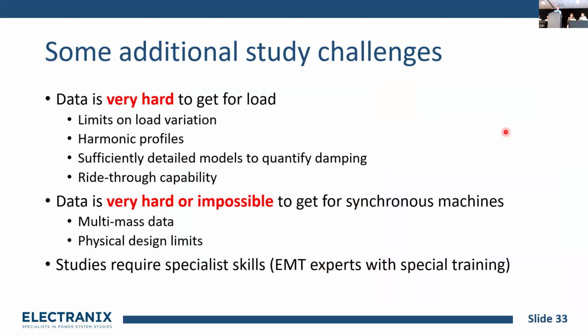With these studies, we don't have that right now. Data is very hard to get, first of all. Load variation limits are very difficult to get and sometimes unknowable. Harmonic profiles are sometimes unknown, at least early on. We don't have sufficient model quality to evaluate damping in the system right now, and there are other model issues - that's another topic we're not going to get into, though a later presentation might talk about it. Ride-through capabilities are also hard to get, and some data is extremely hard or maybe impossible to get. Multi-mass data for a machine you can probably get if you have the right levers to pull, but the synchronous machine physical design limits are going to be a real challenge to get.